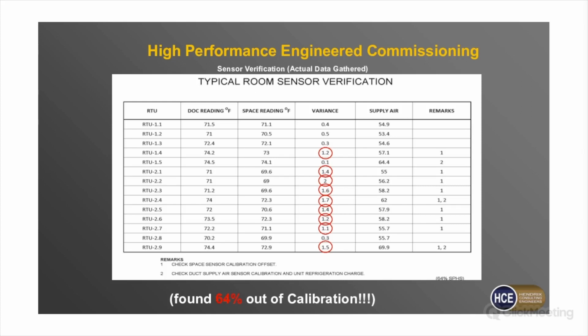The temperature was set at 73, but the entire space was at 68 to 69. This becomes really important as you start to really use the controls to lock down how the building's used. If they're not accurate, you're going to have unhappy teachers, clients, you name it.